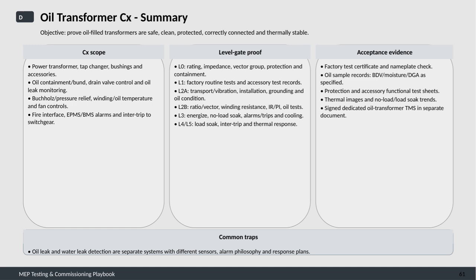At level 0, we confirm the transformer's rating, impedance, vector group, protection, and containment. Level 1 covers factory routine tests and accessory test records. At level 2A, we verify transport vibrations, installation integrity, grounding, and condition the oil. Level 2B involves more detailed electrical tests like ratio and vector group confirmation, winding resistance, insulation resistance, and polarization index, along with further oil tests.